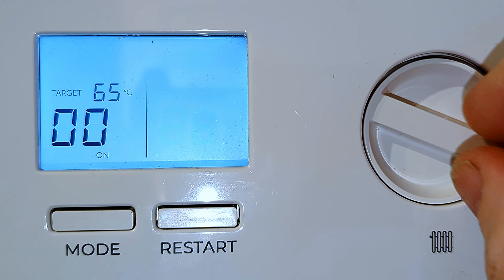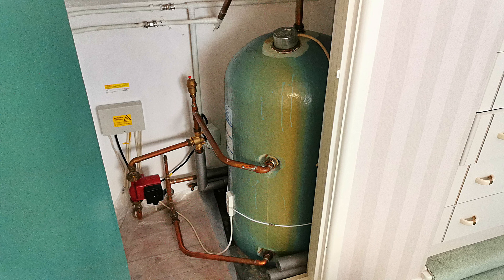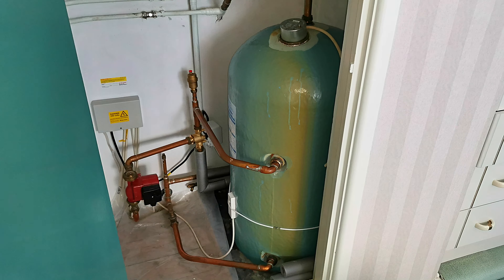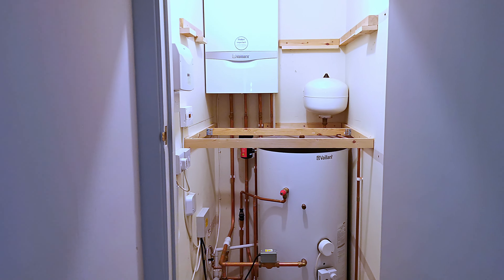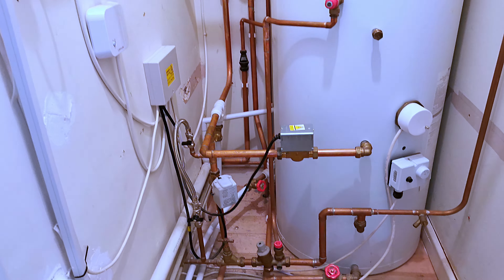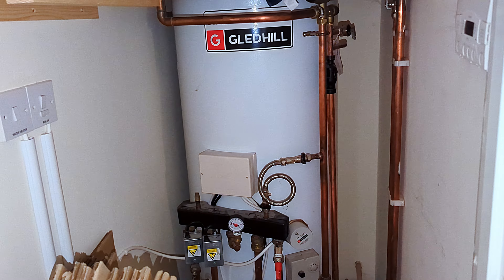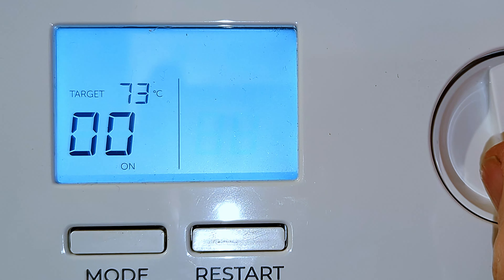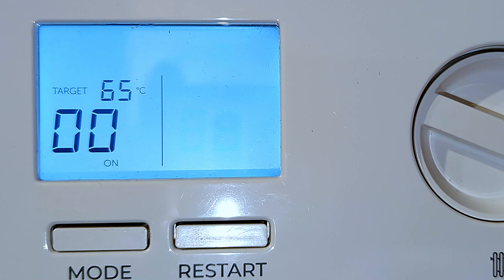Because we have a hot water cylinder, the lowest temperature we should set our boiler to is between 60 and 65 degrees. The reason is that the large hot water cylinder holds stored water, and with stored water there's a risk of Legionnaires' disease. At 60 degrees and above, that temperature will kill any Legionnaires' bacteria that may be in the water. That's why with a traditional system and a hot water cylinder, you should not set the temperature lower than 60 degrees. On this boiler I've set it to 65 degrees.